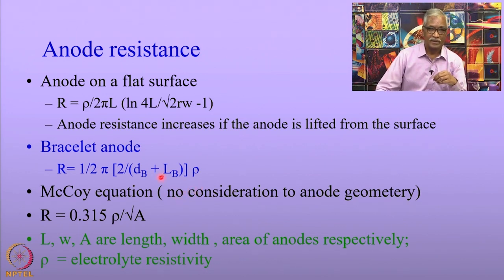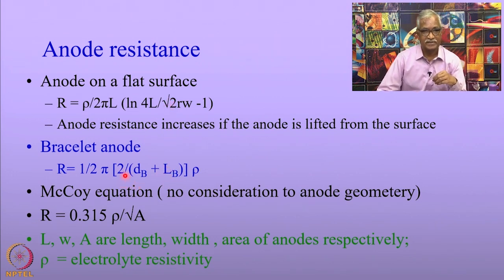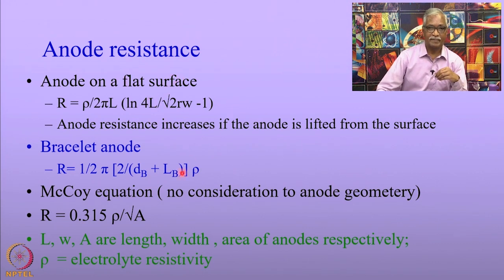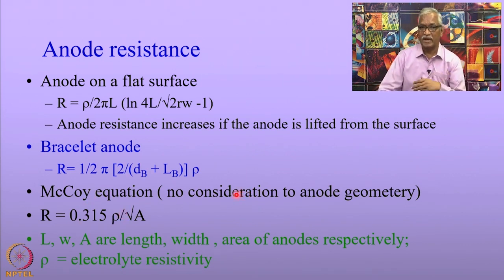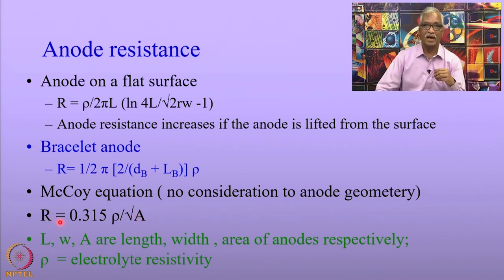If you are going to use bracelet anodes, the diameter and width of the bracelet anode are used in the calculation. The equation to calculate the resistance of the anode changes depending on whether the surface is flat or curved as with bracelet anodes. Very simplified equations are also used — called the McCoy equation — which does not take anode geometry into consideration. All you need is the resistivity of the electrolyte (such as seawater) and the area of the anode to calculate the resistance offered by the anode.